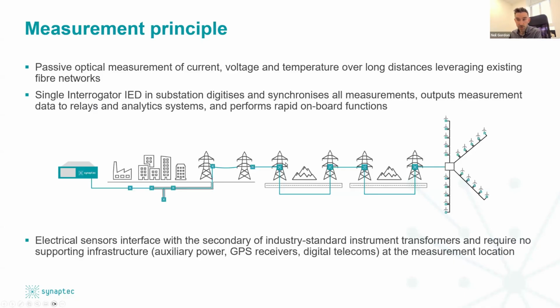You have no auxiliary power at each one of these locations. So there's no power supply, no digital telecoms, no local time sync, no expensive civil works to deploy. They're extremely quick and simple to install while also crucially maintaining compliance with critical measurement accuracy standards. The electrical sensors themselves, which I'll come to in more detail later, interface with the secondaries of standard instrument transformers, CTs and VTs, to allow us to access the primary current or the primary voltage in that circuit. So you can think of this technology on the electrical measurement side as allowing you to use the same reliable, trusted, simple transformers that have been used for decades in power networks in new locations, in remote, hard to reach locations.